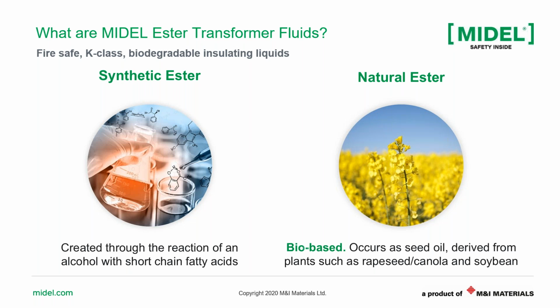Of course, the natural ester is affected by its base oil, in terms of its oxidation stability, pour point, and other parameters. And one item to emphasize as the key difference between a synthetic ester and a natural ester is the oxidation stability. Natural esters should only be used in sealed transformers where there is no exposure to atmospheric air and oxygen.